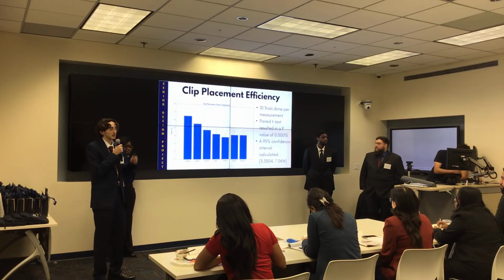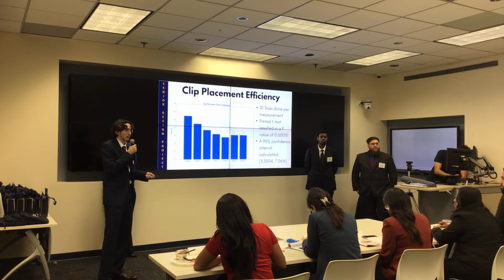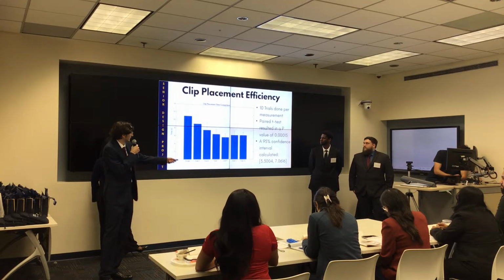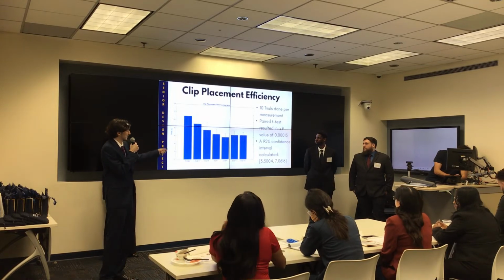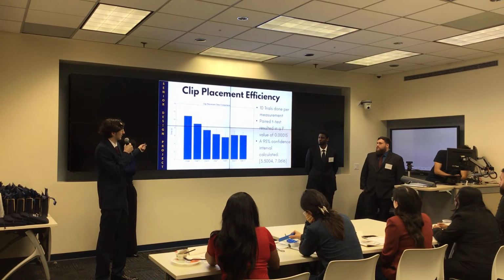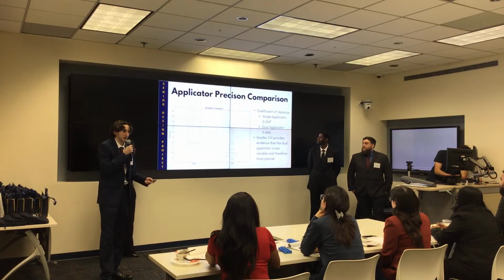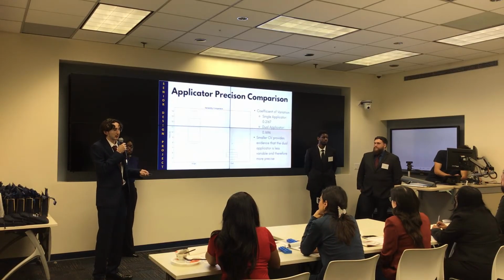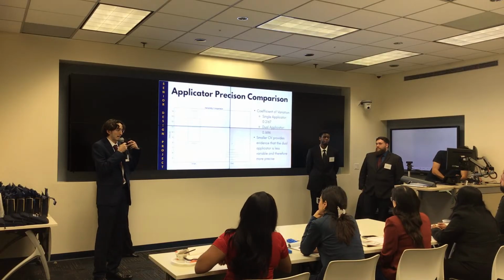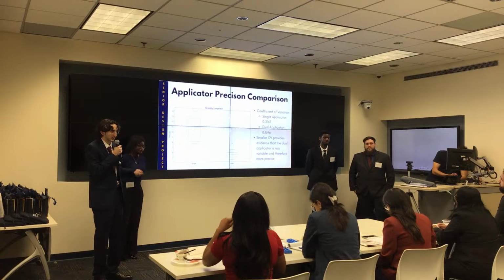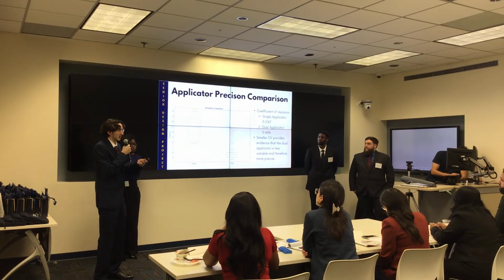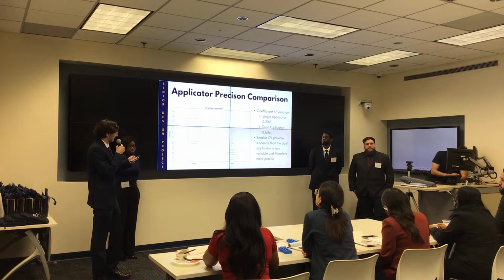Additionally, we measured the time it took to place with the dual clips versus the time it took to place with a single clip applicator. And we noticed that it was statistically much faster to do the dual application across all of the different spacings. This testing was done by a single subject, and it was actually done much faster as the subject became more familiar with the device. As for the precision comparison, we verified that the use of the dual applicator means that the spacing is more controlled and consistent across all placements, and eliminates the uncertainty that comes with using a single clip applicator.